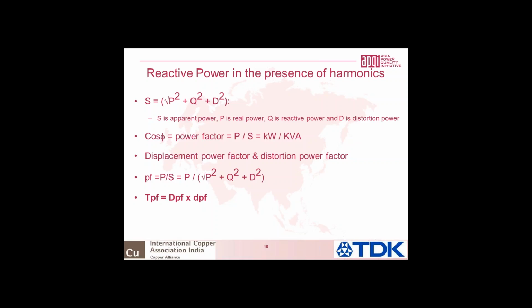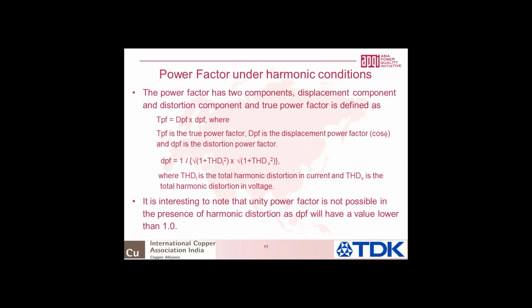And when you look at the equation for power factor, it gets modified. It's no longer P by S, but the S gets changed to root of P square plus Q square plus D square, which brings us to a new definition of power factor, called the true power factor, which is defined as the product of displacement power factor and distortion power factor. Now, let's look at it like this. What you now see is the power factor under harmonic conditions, where it's no longer the phase angle between the fundamental voltage and current, but it is something more. So power factor has now two components: a displacement power factor, which I represented with a capital D, and a distortion power factor, which I represented with a small d.